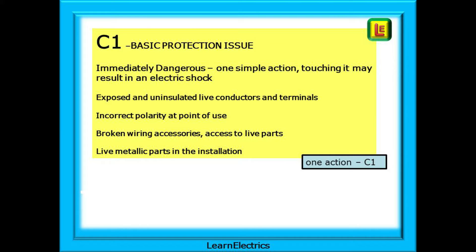What would trigger a C1 code? A C1 is a basic protection issue — it is immediately dangerous. Just touching the observed problem may result in an electric shock or fire. Things such as exposed and uninsulated live conductors and terminals that can be touched, incorrect polarity at the point of use, especially any live wire reversed with the earth or CPC, broken wiring accessories that give access to live parts, or live metallic parts in the installation. I always think of the one in C1 as being just one action to get an electric shock — there is the exposed conductor, there is the danger, one action: touch it.